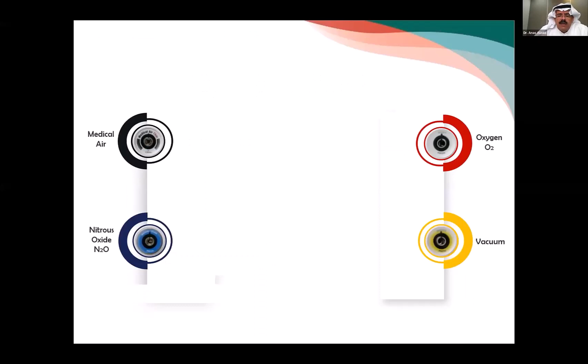There are four medical gases, and if you are using piped medical gases: the oxygen, the vacuum, and the medical air. This is a very quick responsibility if you are using piped medical gases for certain levels of centers. If you are too big, you should go for piped medical gases because it will be more economical for you, and for safety, too many cylinders being moved is dangerous. So piped medical gas will be your viable solution. The four gases used are the oxygen, the vacuum, the medical air, and the nitrous oxide, and they come from different sources.